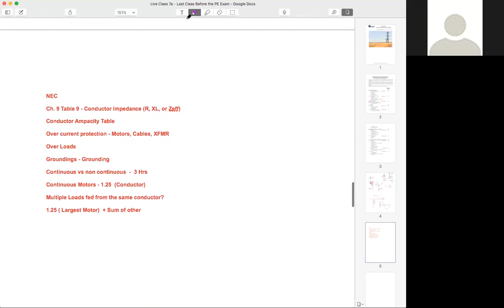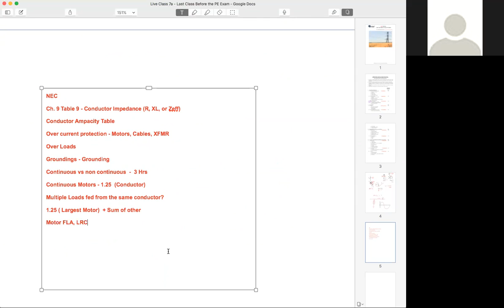Another good one I can't believe I forgot is motor full load amps. Motor full load amps and motor locked rotor current are two big ones. Make sure you know where that's at, make sure you can get to it, make sure you can use it. And also make sure you read the table titles.